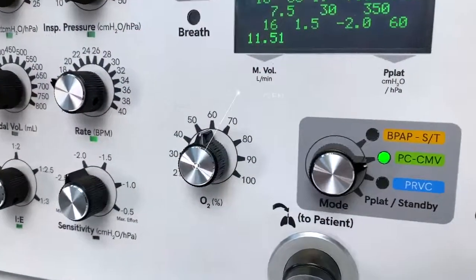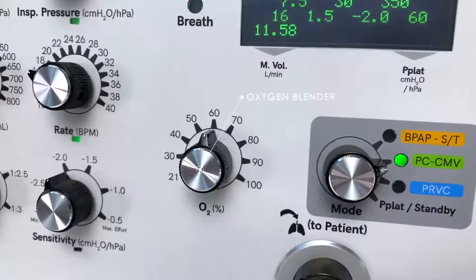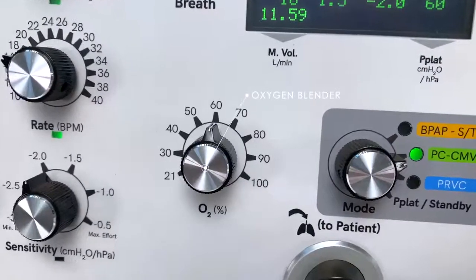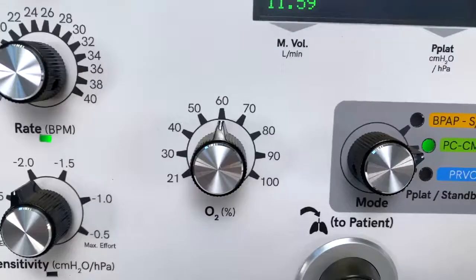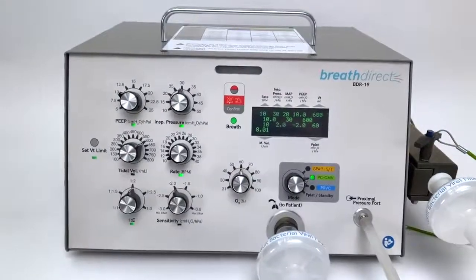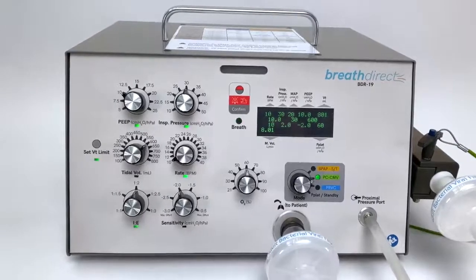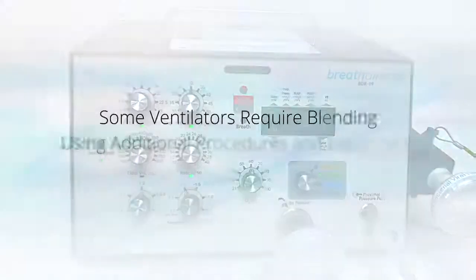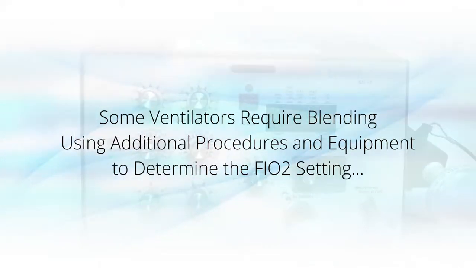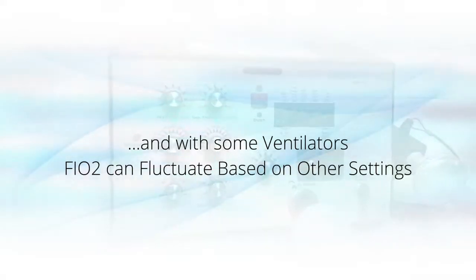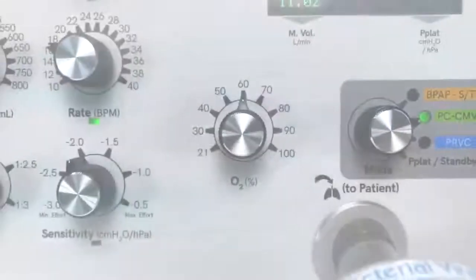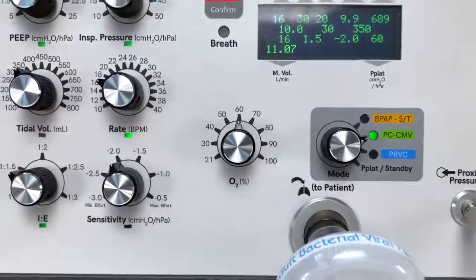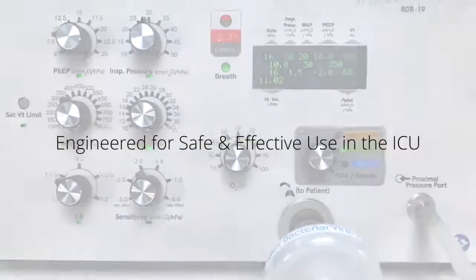Of note, the BDR-19 ventilator has an internal oxygen blender, and the FiO2 can be set at 21% and from 30 to 100% in 10% increments. Importantly, the FiO2 setting does not influence the other controls, and the other controls do not influence the FiO2. With some other ventilators, oxygen has to be bled into the ventilator circuit, causing the user to resort to additional procedures and equipment to determine the FiO2 setting. And the FiO2 level can fluctuate based on how other controls are set. The BDR-19 FiO2 control is independent of other controls, which facilitates convenient, safe, and effective use in the ICU critical care setting.